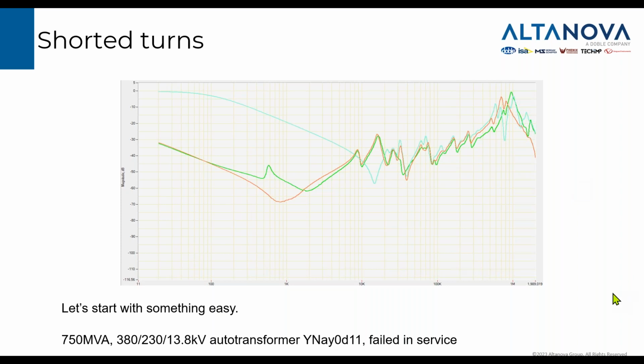I didn't say before, there is a technique called the short circuit test. This is made by doing the same tests, but with other windings shorted. If you do it that way, these traces will look like this trace here. But this was an open test. The other winding was not shorted, and we were still getting a similar response.